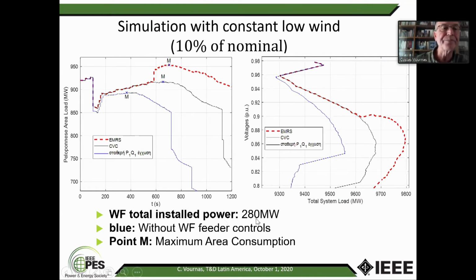So you see here the cases where the blue curve is without wind farm representation. The initial case is the same, but there is no change in P and Q injection from the wind farm to the transmission system at the point of common coupling. So you have a maximum power in the area of Peloponnese. This is the total load in Peloponnese in terms of simulation time. Initially it was above 900, 925. Then the maximum without help from the wind farms is below 900.